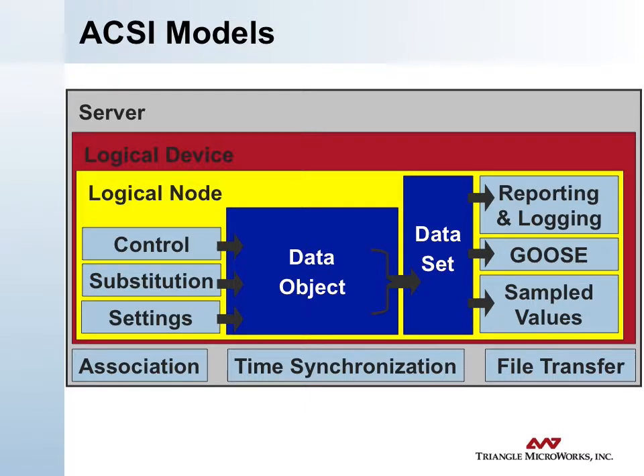This diagram shows the organization of the ACSI models and their scope. The server represents a communications capability at some address. The services you do directly with a server include the ability to associate or make a connection with it, to do time synchronization, and to do file transfers. These abstract services operate at the server level. Within a server are multiple logical devices, which may or may not correspond to different physical devices behind the server, depending on how you organize a gateway.